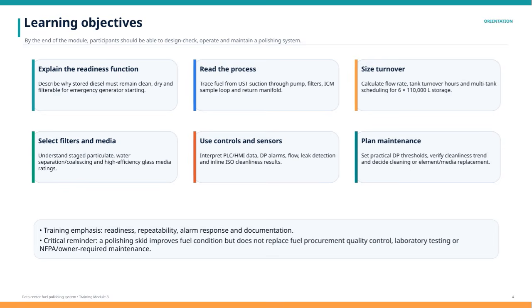tanks. You'll get a solid grasp on selecting the right filters and media, including staged particulate filtration, water separation and coalescing, and the importance of high-efficiency glass media ratings. You'll also learn to use controls and sensors by interpreting PLC and HMI data, understanding differential pressure alarms, flow monitoring, leak detection, and inline ISO cleanliness results.